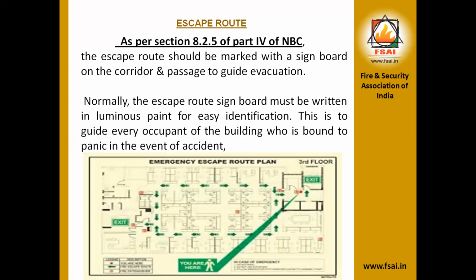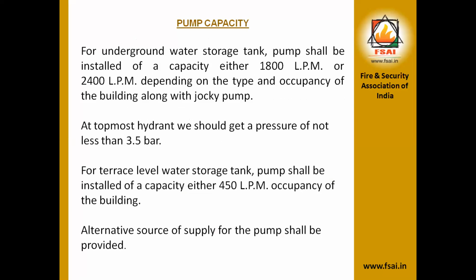For underground water storage tank, a pump shall be installed of a capacity of either 1800 liters per minute or 2400 liters per minute, depending on the type and occupancy of the building, along with the jockey pump. At the topmost hydrant, we should get a pressure of 3.5 bars. So at the time of fire audits, the fire departments go through all these norms which I have specified. So as a student also, you should know what the pressure at the top should be, which is 3.5 bars.